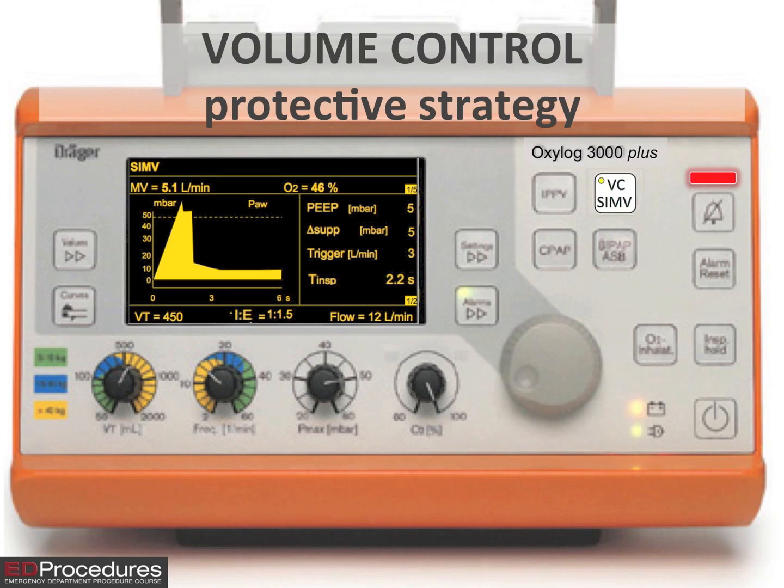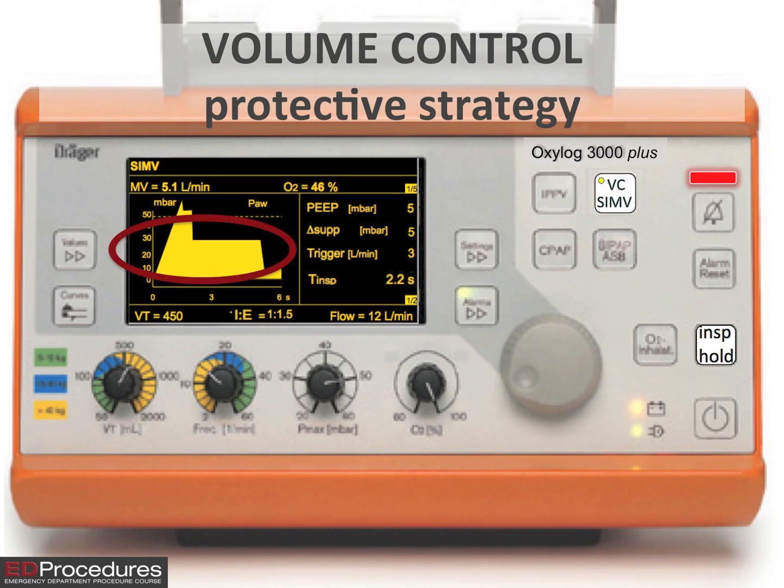Earlier on, I said the Pmax or PIP alarm was meaningless in itself. That is not to say it should be ignored. High PIPs may just be in the trachea, but it may reflect high pressures in the lung itself. You can figure out which it is by doing what's called an inspiratory hold maneuver, by holding down the inspiratory hold button. It does what it states. A breath is taken and held, allowing pressure to equilibrate across the entire lung. This is called the plateau pressure.